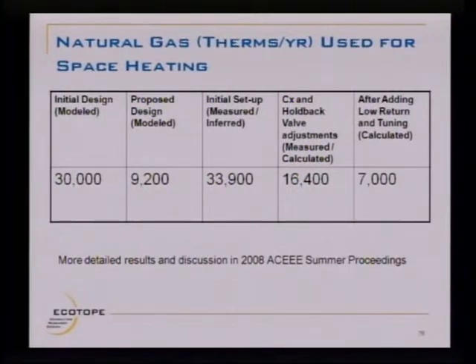Initial model, this is in therms per year, 30,000. When the building was first opened up, it was using more than the initial model by quite a bit. And oh, I'm sorry, when I say the initial design there, that was the design of the store before our client took over and before we proposed this whole range of energy efficiency measures. So what we predicted would be used is about 9,000. Right out of the box, it was using 34,000 therms a year. After the commissioning, which we found that the holdback valve wasn't installed and adjusted, that dropped it to 16,000. And then after adding the low return, it was down to 7,000.